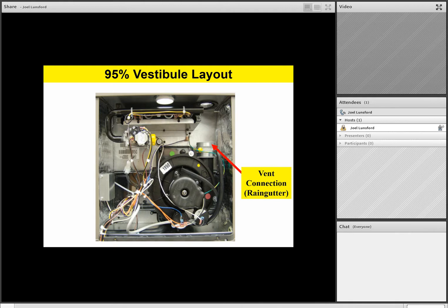Here's a neat feature we have. We call it a rain gutter on our vent connection. That rain gutter feature allows water to collect in a rain gutter and then run down the drain instead of going into the induced draft blower. So that's a pretty neat feature. That rain gutter feature actually prevents or greatly reduces the amount of water that can get back into the induced draft blower by catching it as it comes down the exhaust pipe.